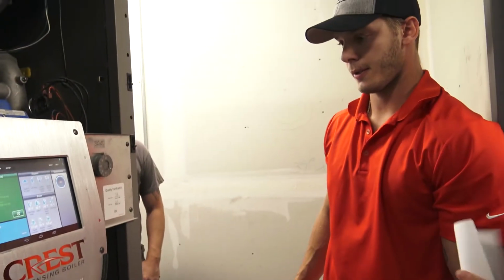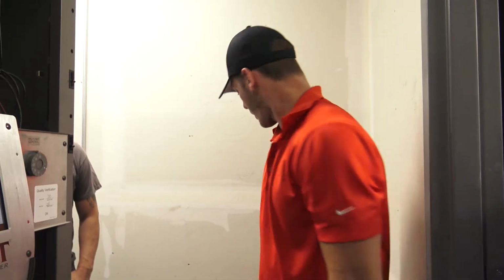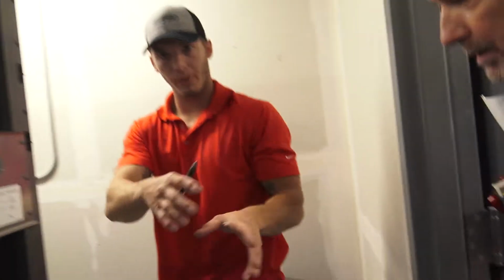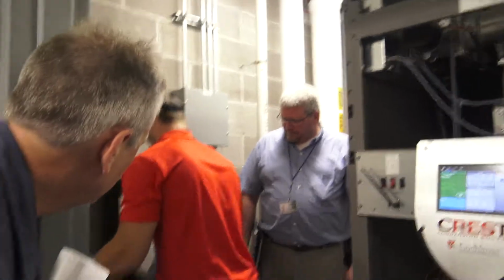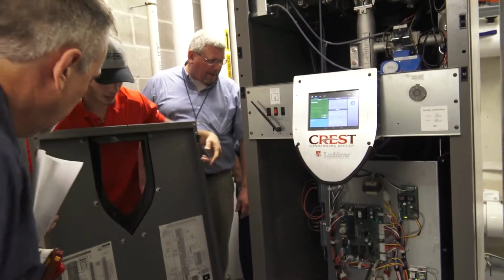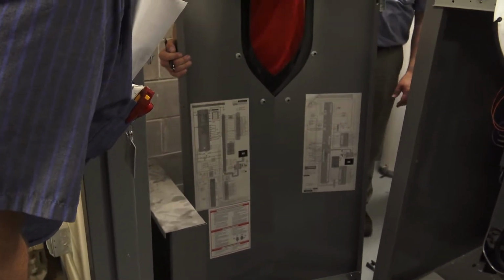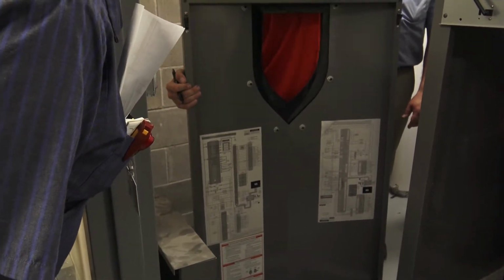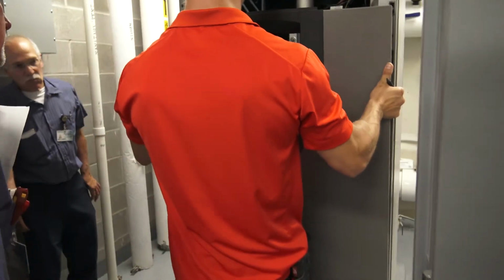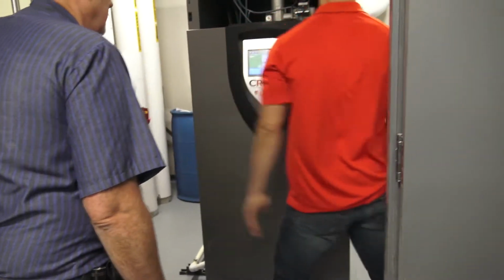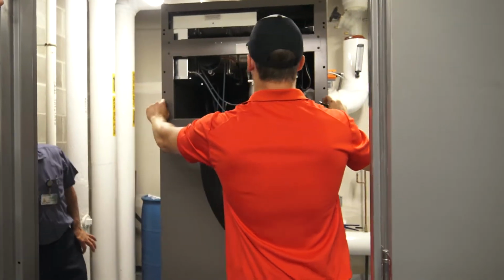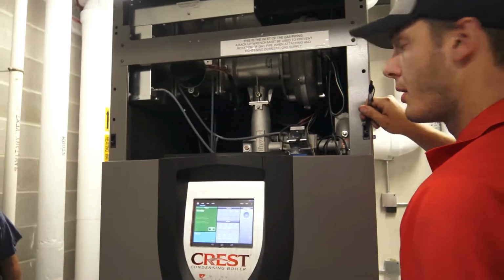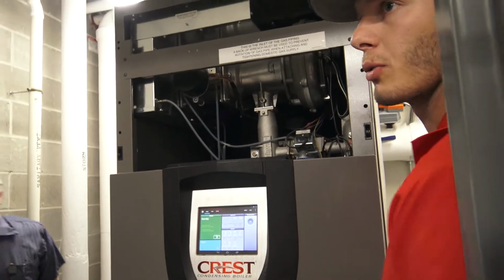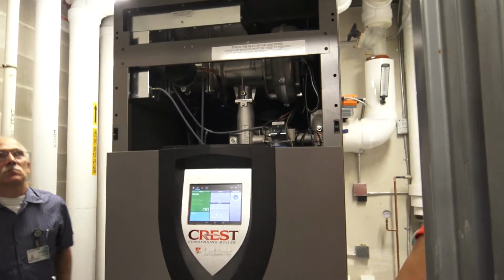Any trick to getting these front doors off, panels off? So you got them sitting over here. You're going to start with the bottom door on, and when you take them off, you're going to take the top off first. You'll see that the bottom is hinged like that. The hinge wants to go over that front lip. But also there's a little lip right here. It has to go over the top of this as well at the same time. So I take my knee, place it in there, kind of hold it high. Make sure that these clips are pointed out. Sometimes the springs in here can break. You just have to pull it out with your finger and make sure that you don't smash it down there. So down in the top as well.